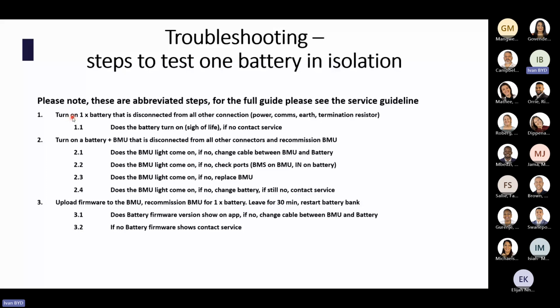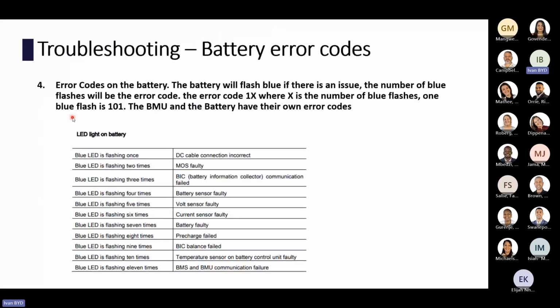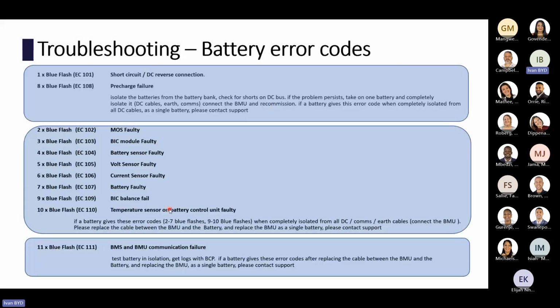And here's the error codes on the batteries. They're sorted into various categories. I've just sorted them into categories. So some error codes installers can do things with and some can't. For example, short circuit or DC reverse connection is something that can possibly be sorted on site, where if there's a short or anything on the system, the battery will detect that. And same for the pre-charge failure. Any of these error codes, that's not something that the installer can necessarily do on site. Either parts will have to be sent to them, or the battery will have to come to us.